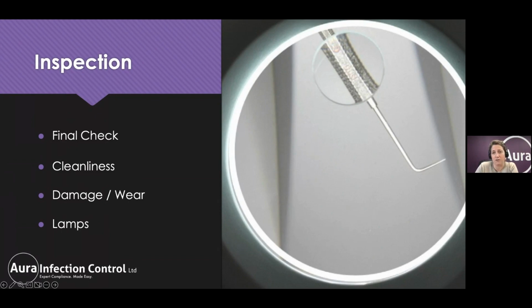There is no pitting or damage or rusting. There are no breakages, and everything that you're passing by this inspection point is safe to be used on a patient. You need to make sure your lamp ideally has two dioptres, so it has the main magnification and then an additional magnification as well.